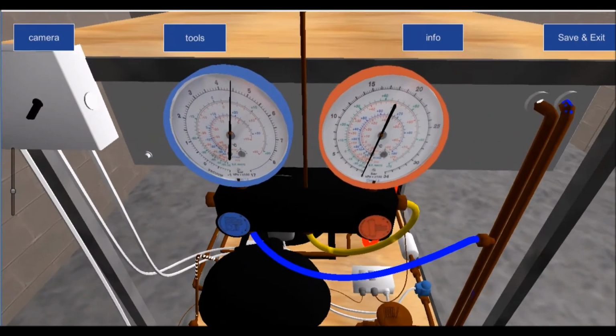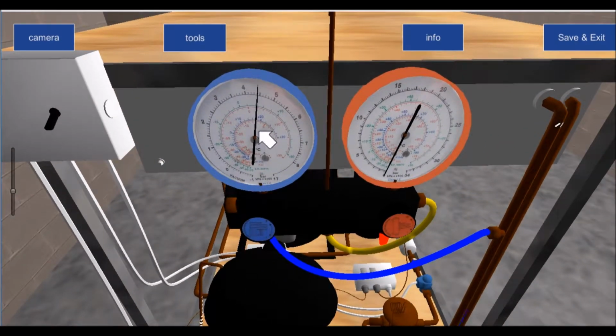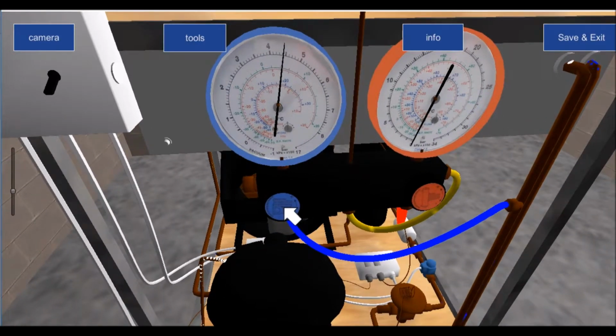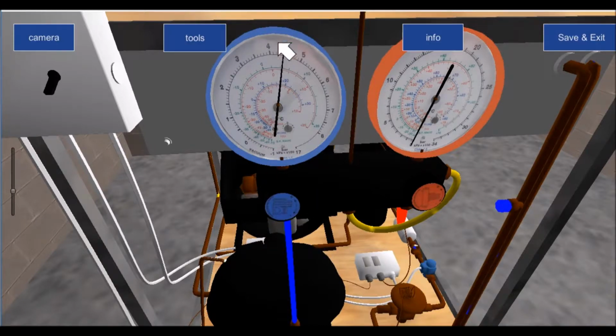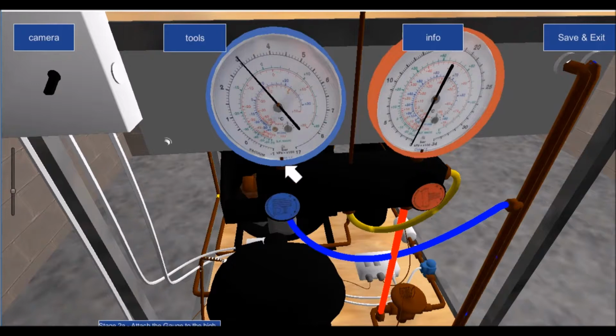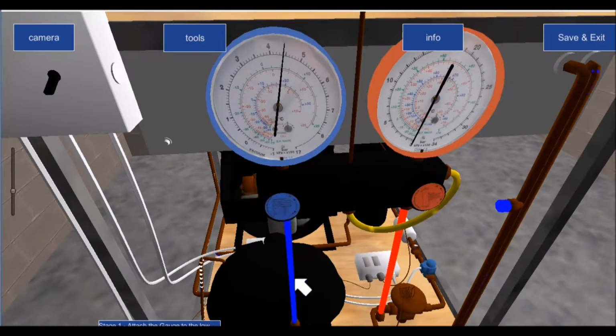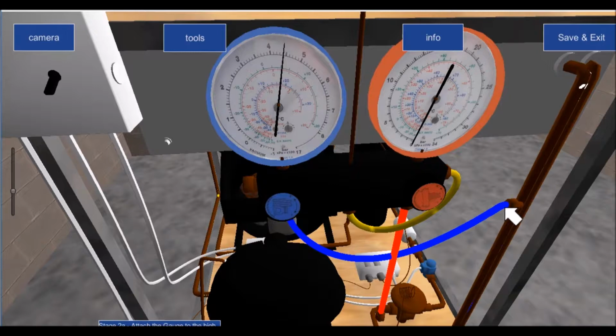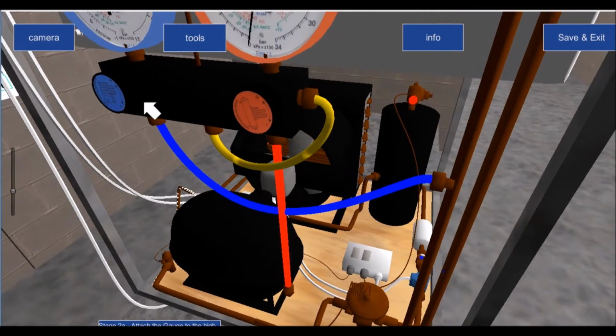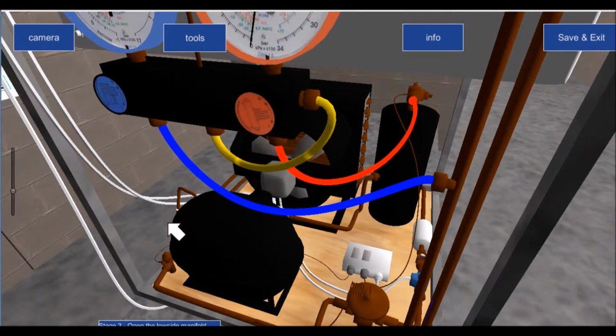Now, effectively, if I want refrigerant to go from this side here into my manifold and into my red hose line, I have to open the valve here, which it is not allowing me to do because I'm not in the purge sequence. So maybe I need to just do this sequence here for the sake of it. Okay. So literally we go again, we see pressure going straight through when I open this one. Apologies, because I'm not doing the steps it wants me to do, because I'm in a fierce hurry altogether. Terrible to be young and enthusiastic.